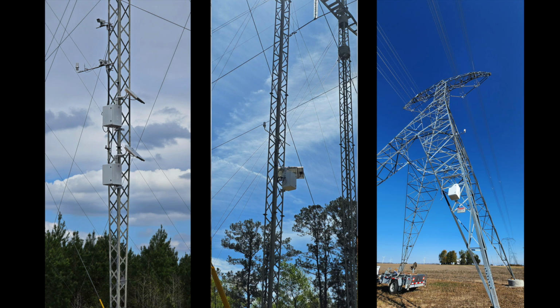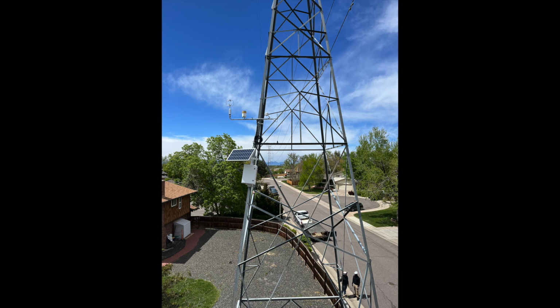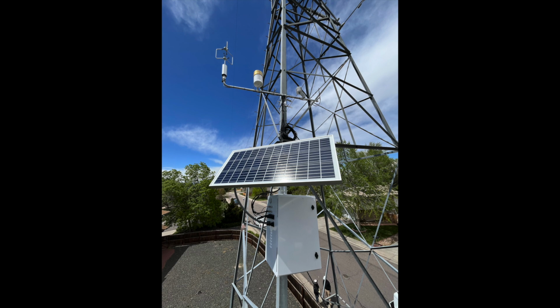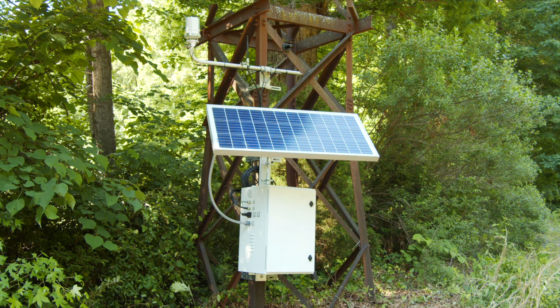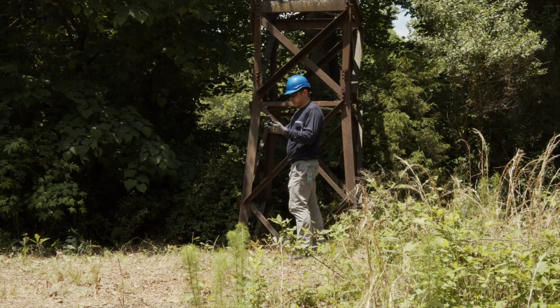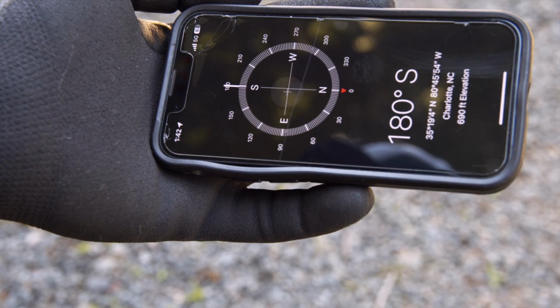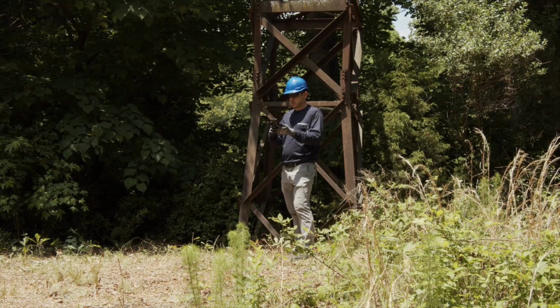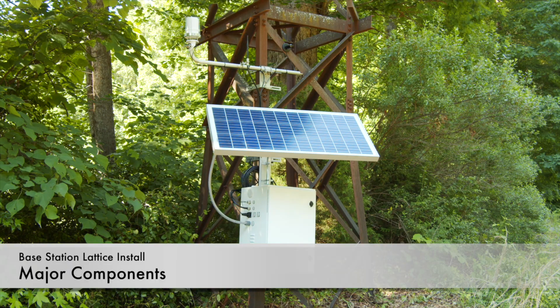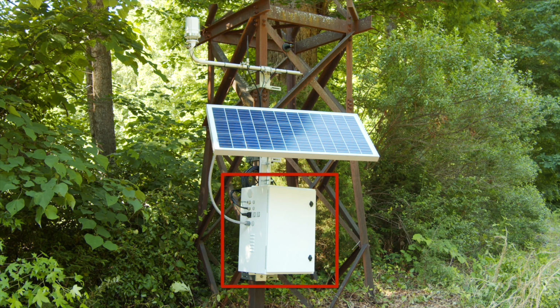of the base station, as RF monitors should be within line of sight and less than 900 feet away or 300 meters. If line of sight is not possible, range will be reduced. For longer ranges or challenging installations, contact EPRI to discuss the possibility of using a repeater. Confirm that the solar panel will be able to face south in the northern hemisphere and north in the southern hemisphere. Major components: electronics cabinet and battery, auxiliary mount, solar panel.